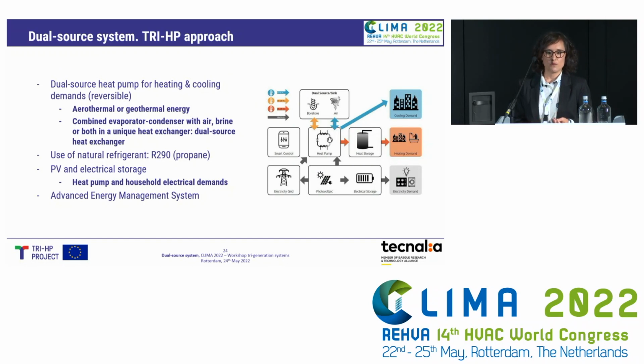So what is the TRI-HP approach for this dual source system? Well, the main innovation is the dual source heat pump, used for heating and cooling. It is a reversible heat pump, and it's using geothermal and aerothermal energy as a source or a sink for the heat pump. The main innovation is that it's using a combined evaporator condenser with air, brine, or both at the same time in a unique device, in a unique heat exchanger, the so-called dual source heat exchanger.